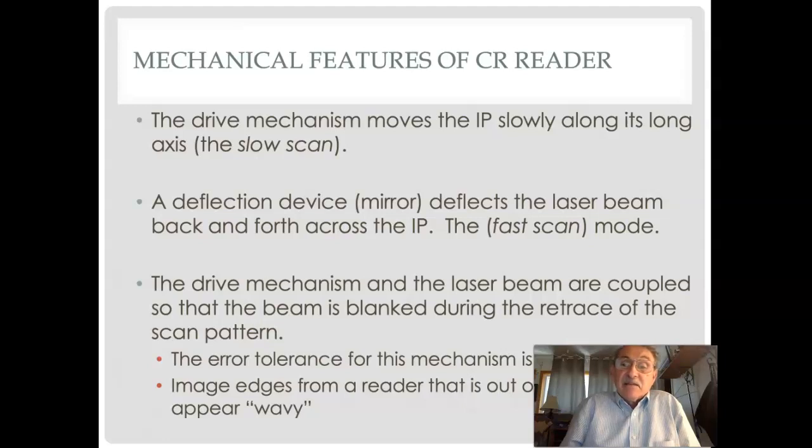The error tolerance for this mechanism is in fractions of a pixel. And so you can imagine that it is adjusted very carefully and very closely. If we have image edges from a reader that's out of tolerance, then they may appear wavy, and we understand that that is a drive mechanism artifact, and a clinical engineer would be required to adjust it.